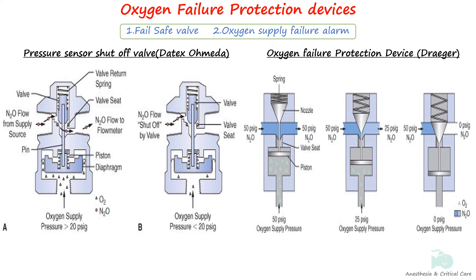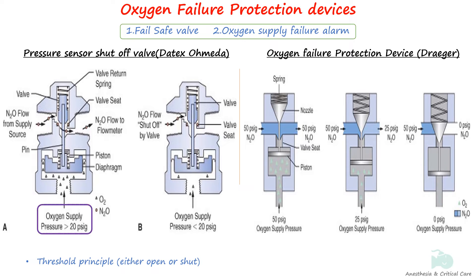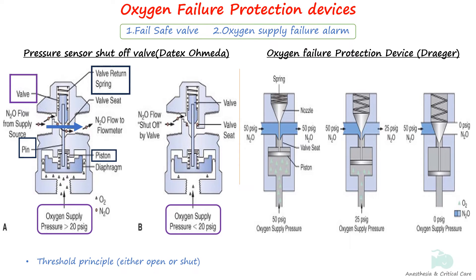The pressure sensor shutoff valve, used in machines like Datex Ohmeda, operates in a threshold manner — the valve is either open or shut to allow the flow of nitrous oxide depending on the oxygen supply pressure. In diagram A, oxygen pressure moves the pin and piston up, opening the valve and allowing nitrous oxide flow. When oxygen pressure falls below the preset level, as shown in diagram B, the force of the valve return spring closes the valve completely.